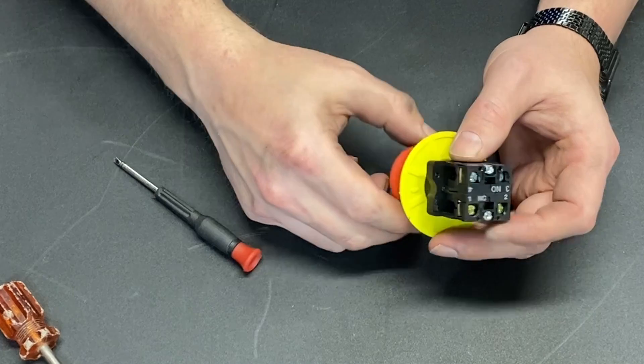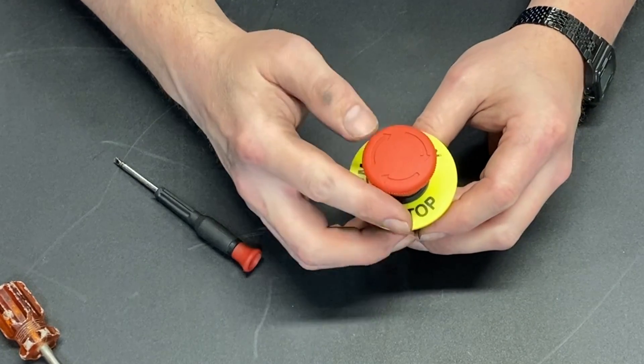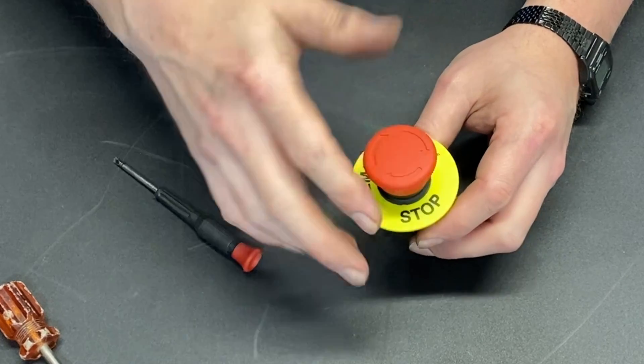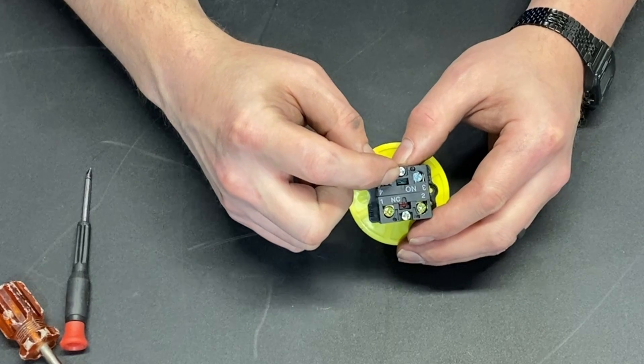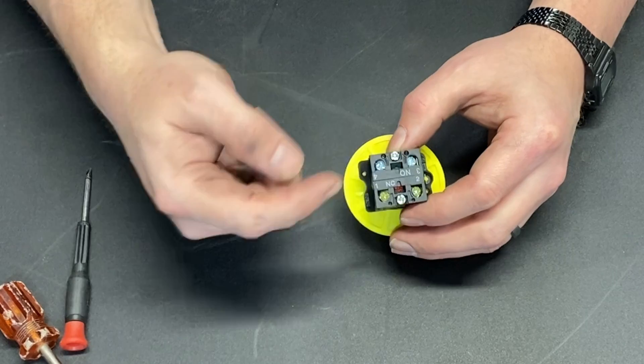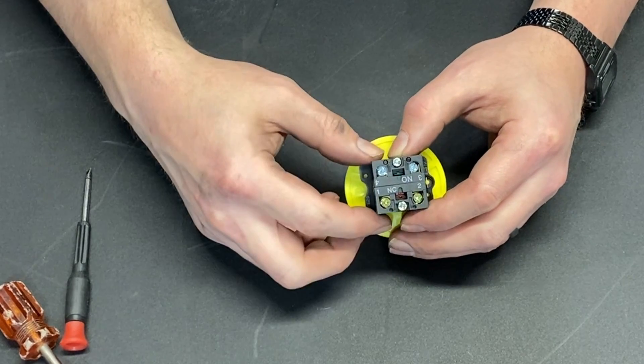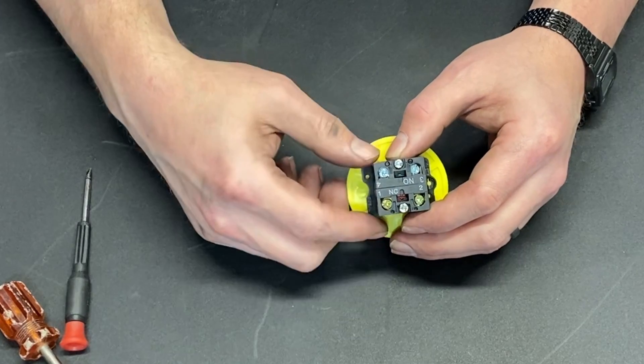So what that means is when it's in the running position, so we haven't hit emergency stop, so it's out, it's doing what it's supposed to do. Normally open is not going to make a connection. The connection is going to be open. Normally closed is going to be making the connection. The connection between this terminal and this terminal is closed, meaning we have continuity.